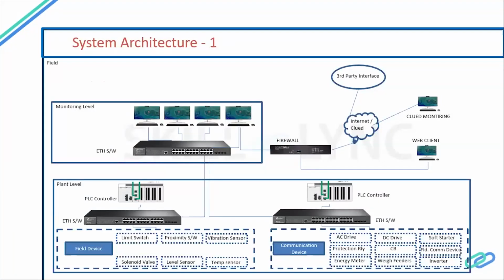Basically, this is system architecture one. If you see here, these are the field devices. Field devices may be limit switches, proximity sensors, vibration sensors, solenoid valves, level sensors, temperature sensors. These field devices are directly connected with your PLCs, and the PLC is directly connected with your Ethernet switches. Field devices are also directly connected with your remote IO. Remote IO is connected directly to Ethernet switches. Ethernet switch is directly connected with PLC controllers. These are the field devices which are connected with your physical inputs.